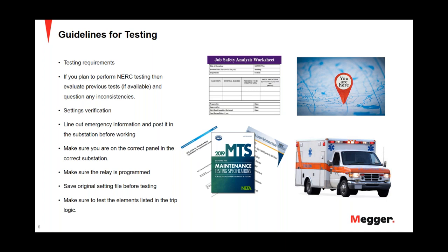If there are any changes that need to be made, let them know so we can make the changes in the relay while we're there, and then go ahead and start performing the test. That way the test results will reflect the new settings. It's good to have a note in there as well — new install of settings, setting changes were applied to relay on this date — so it documents what you've done as a test technician. The documentation trail is huge.